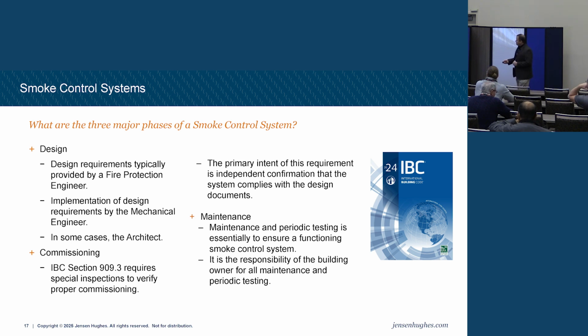Nah, they're all good. But mechanical has to be involved, because the equipment has to be capable of doing it. And I'll give you an example. The old pneumatic systems, a lot of those pneumatic solenoids are not fast enough to comply with the requirements of smoke control systems. They open too slowly. And if I have pneumatic dampers in one area because those are legacy, and now we're putting in everything else as electric actuators, and then I kick all the air handlers on for an exhaust system, but my pneumatic opens too slowly, I can pull doors off frames, I can break windows, I can cause problems, I can collapse ductwork, right? So the whole system has to work together and in the time requirements that are necessary.